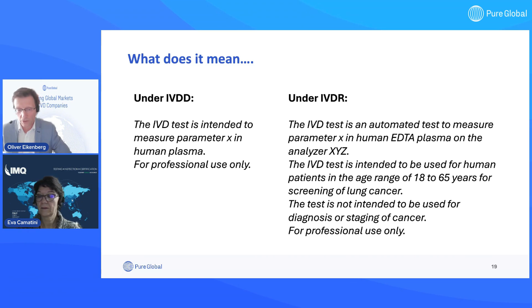So manufacturing or marketing wants to continue with this broad intended purpose because the limitation might also limit their sales. However, regulatory needs to define this. I already mentioned the paragraph, but it is also reflected in many others, like IVDR Article 7 or in the classification rules, where this might lead to a higher classification. And of course, you also have this control, for example, in clinical performance studies or PMPF studies, during the ethics committee or national competent authority review. So in the end, there's no way to continue with the old concept of the analytical intended purpose. You need to change this, but I know that there are significant discussions ongoing between marketing and regulatory departments in IVD companies.